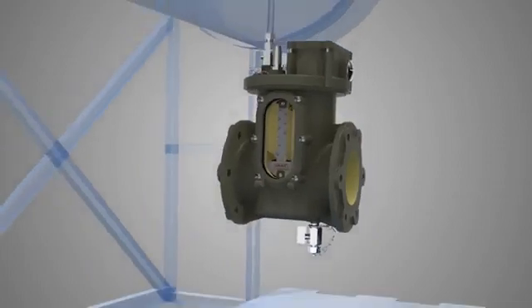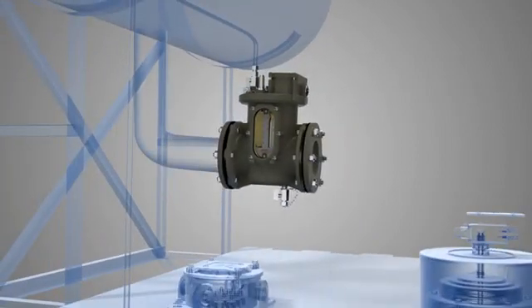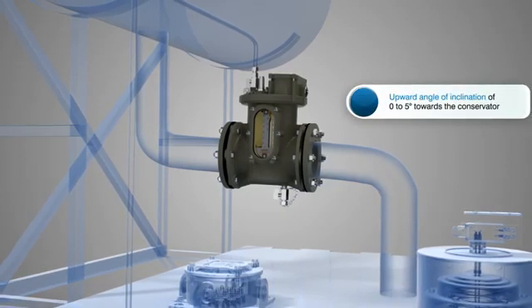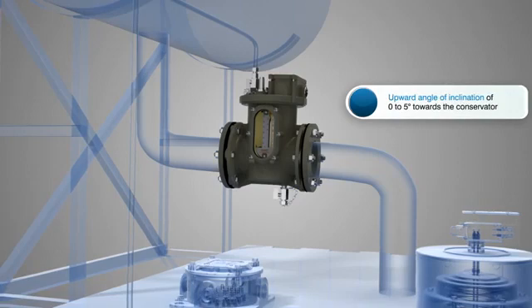It is installed in the pipeline connecting the oil conservator to the transformer tank at an upward angle of inclination of 0 to 5 degrees towards the conservator.